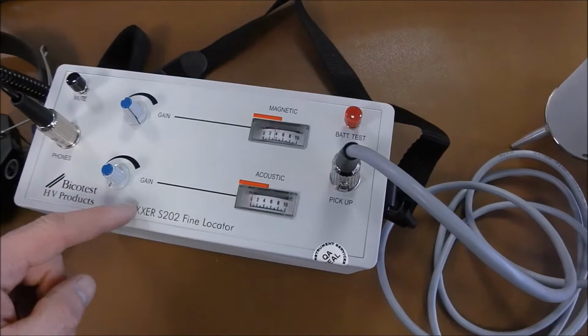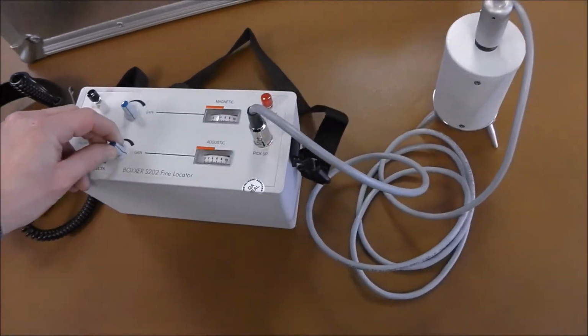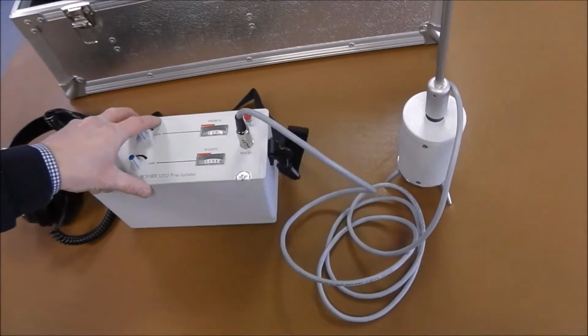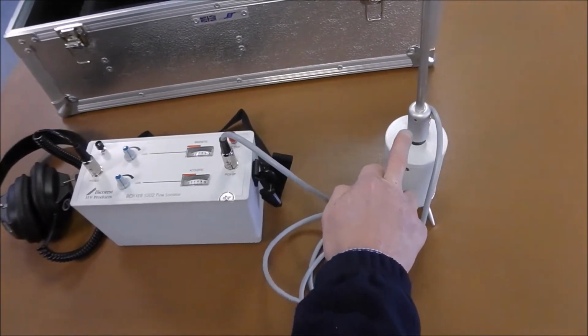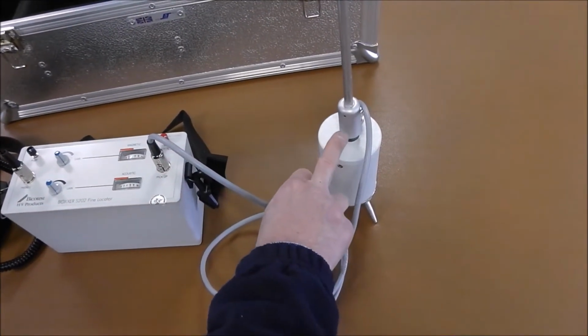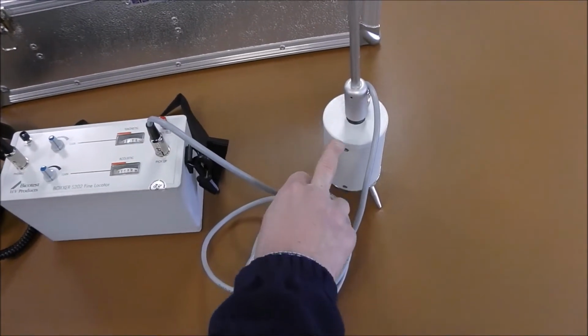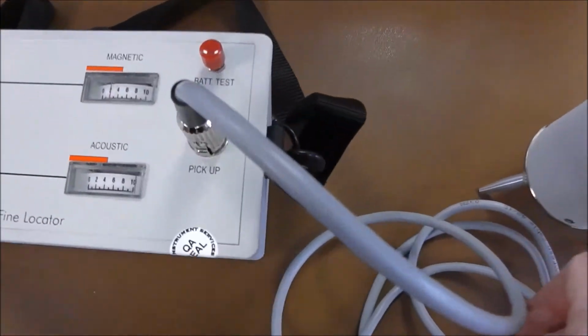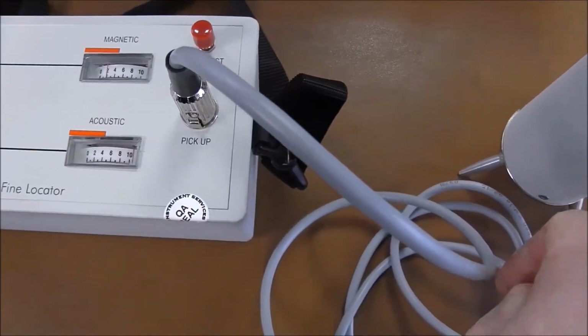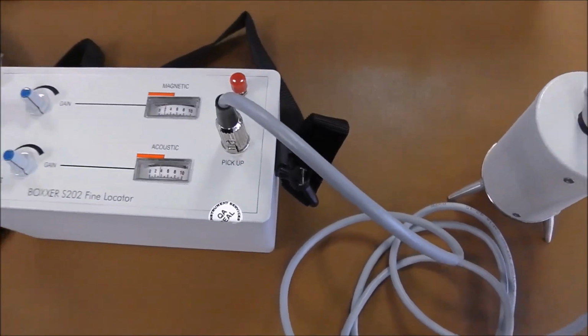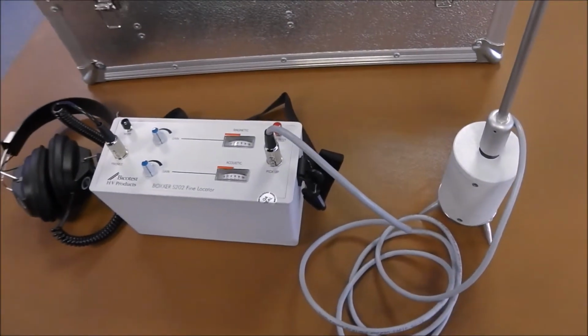Set the acoustic pickup on the ground and rotate the acoustic channel gain control clockwise to increase sensitivity. Acoustic signals are now picked up which are audible on the headphones and displayed on the acoustic channel meter. Tap the ground in the vicinity of the pickup to give identifiable signals. Check that the mute switch functions whilst pressed.